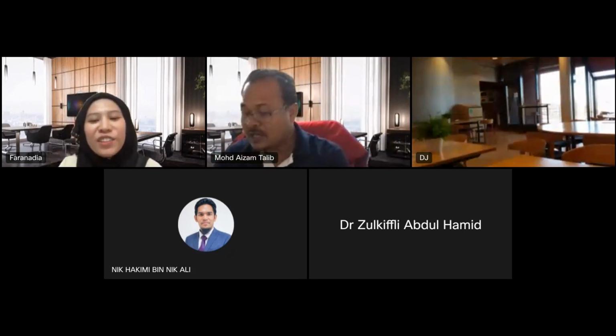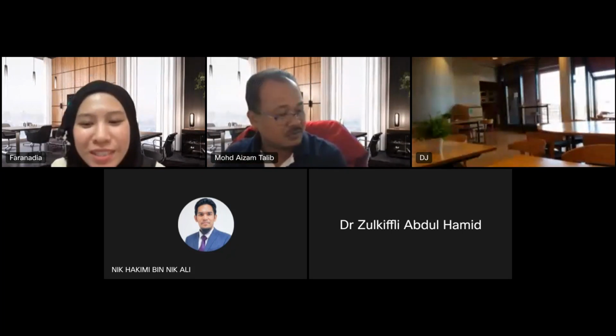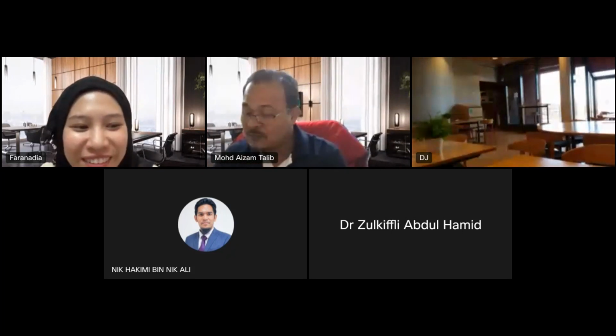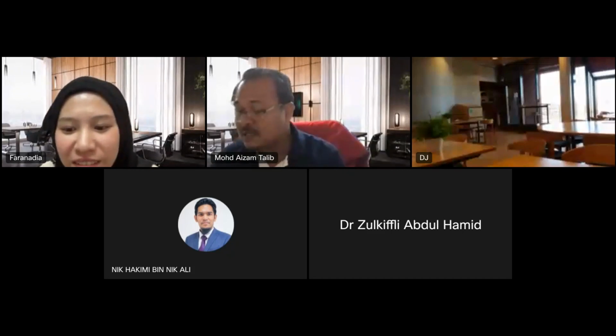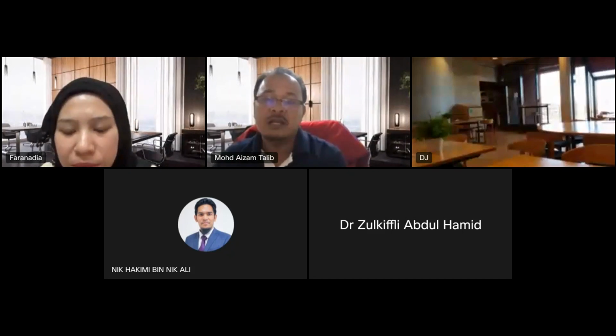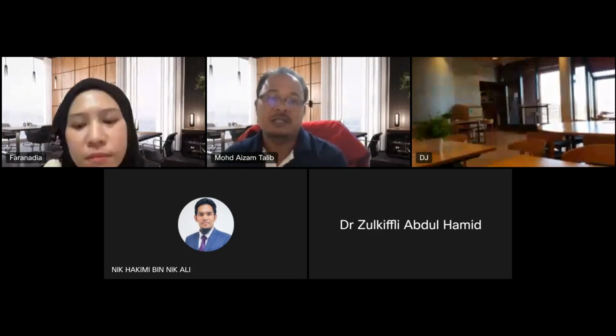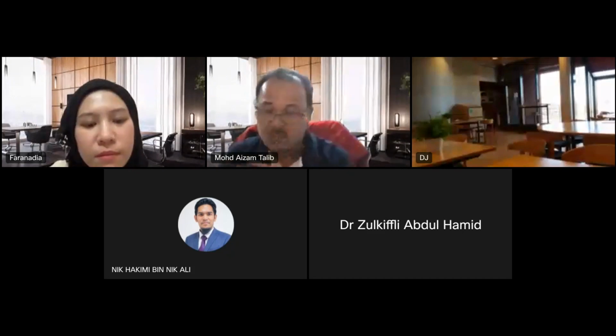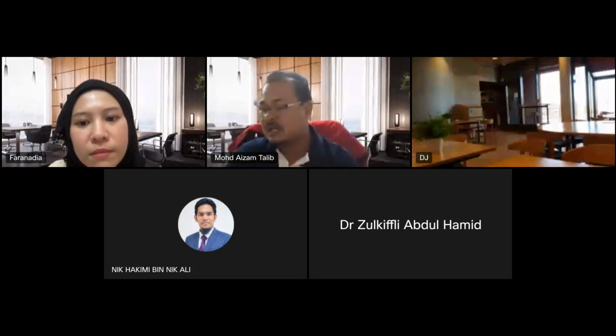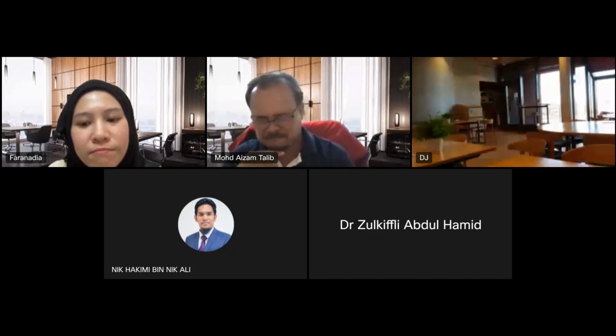Okay, Dr. Azam, then we have 3 more questions. For the mechanical, mechanical is more on the acoustic. It is purposely to locate the source of the fault. We are not able to locate the fault based on the chemical and also based on the electrical. Only through this mechanical, it means through this acoustic method.